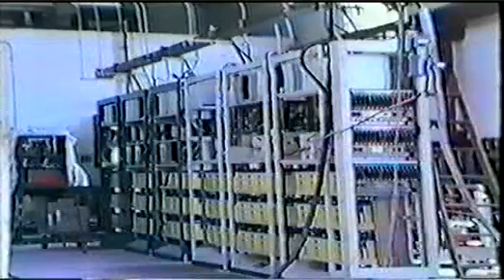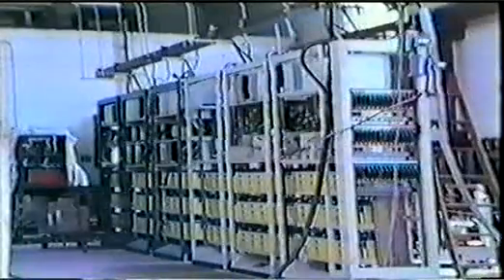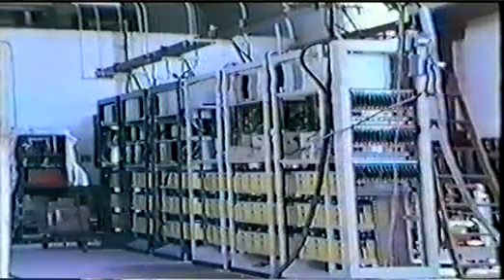There is not any damage to the battery cables within the racks. So it would seem that the shunt is the weakest link in the chain, and that's what would go. Connecting racks together in reverse polarity also only blew the cable shunts.